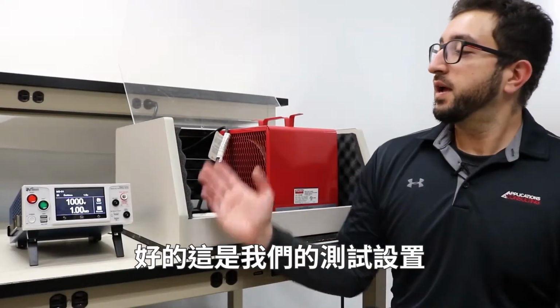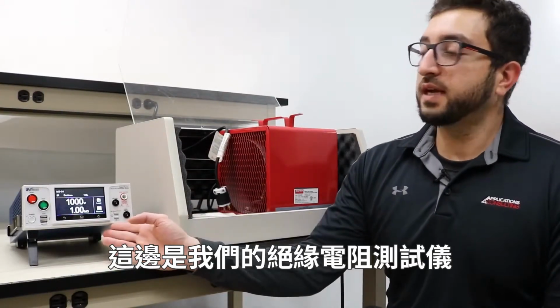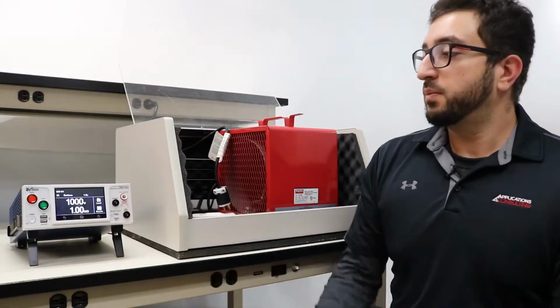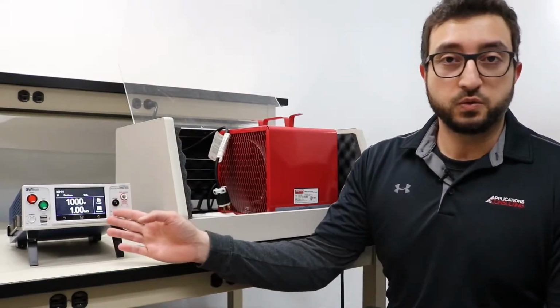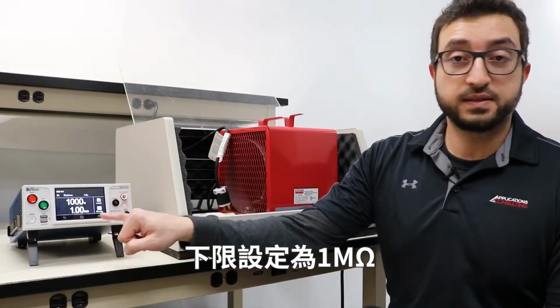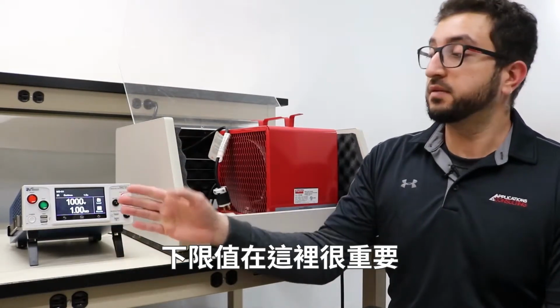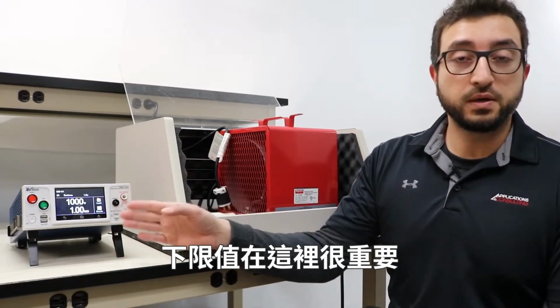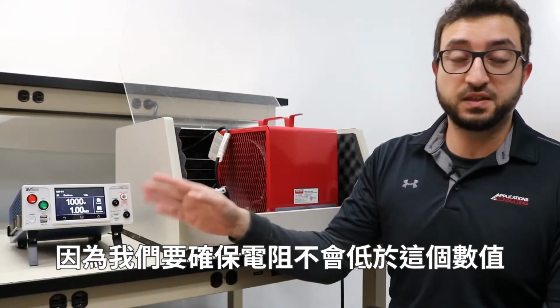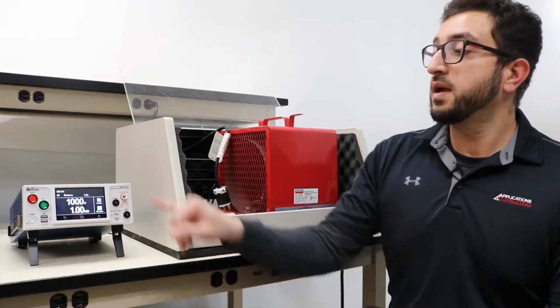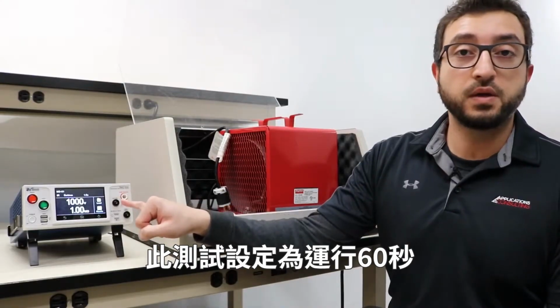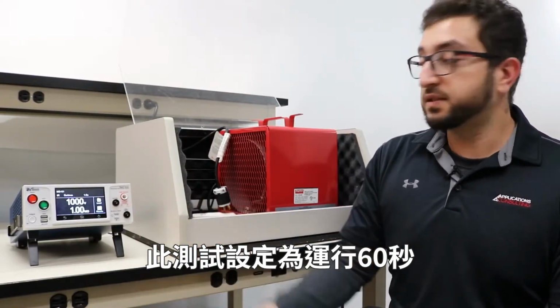Okay, so here's our test setup. On this side, we have our IR tester programmed at a voltage of 1000 volts and a low limit set to 1 mega ohms. And the low limit is what's important here because we want to make sure that the resistance does not fall below this number. And this test is programmed to run for 60 seconds.